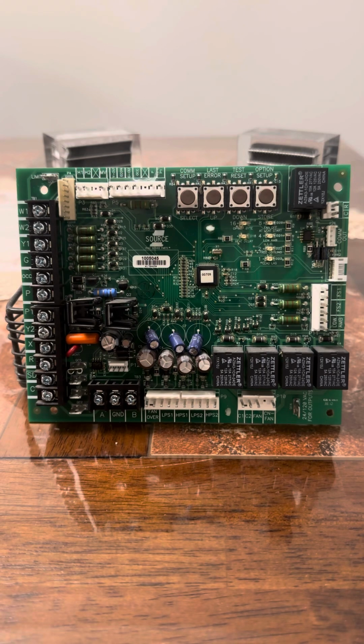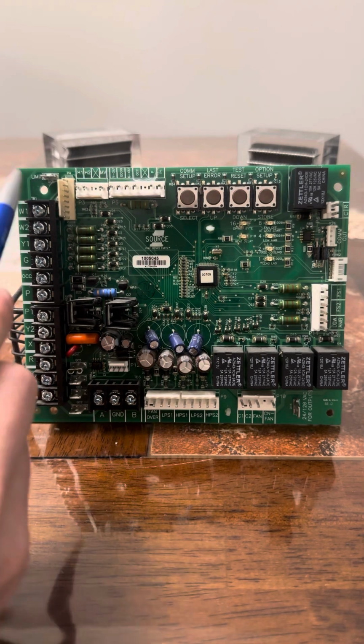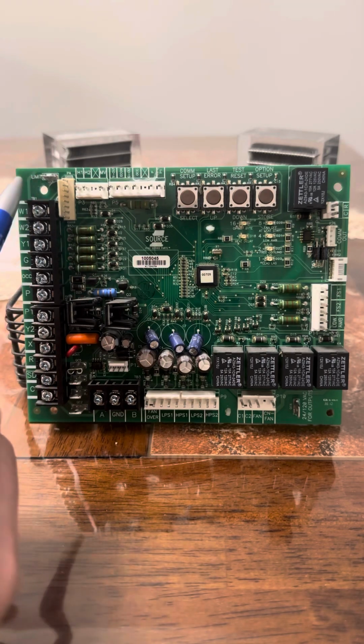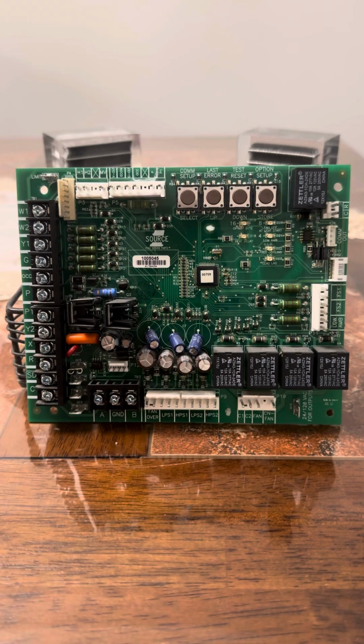There is a method of actually changing the fan delay on this board to increase the fan delay for when the blower turns off. You can increase it to 180 seconds, and I will do a video demonstrating how to do that later on. But today I just wanted to talk about the reasons why you could be getting a 9 flash code here on this limit terminal.